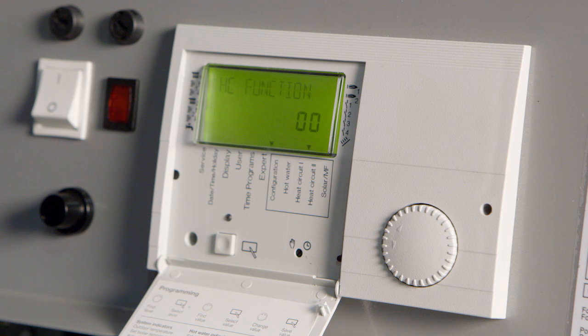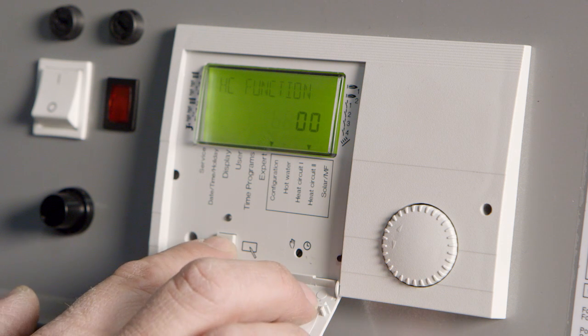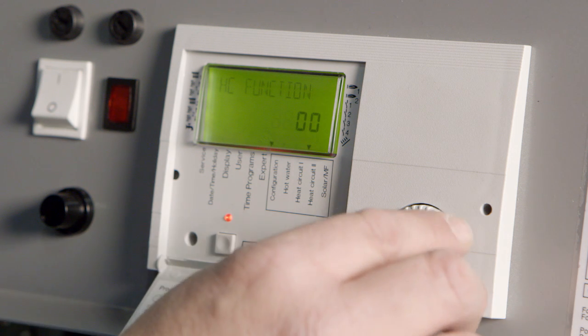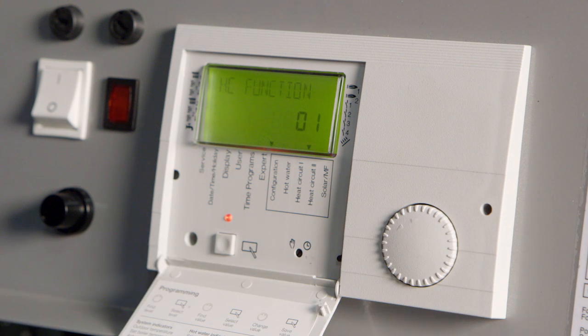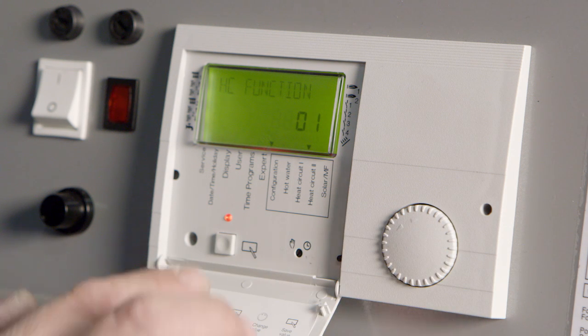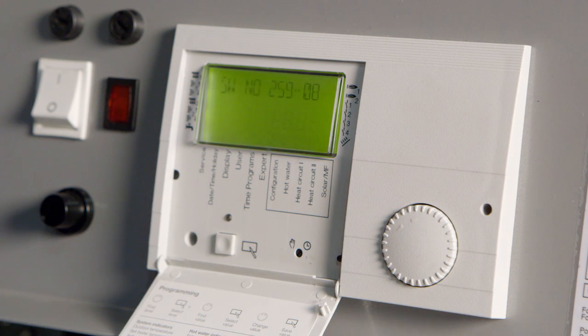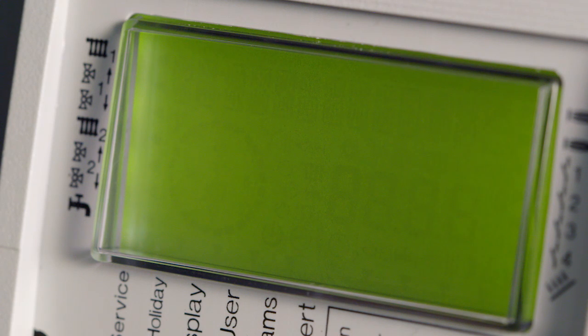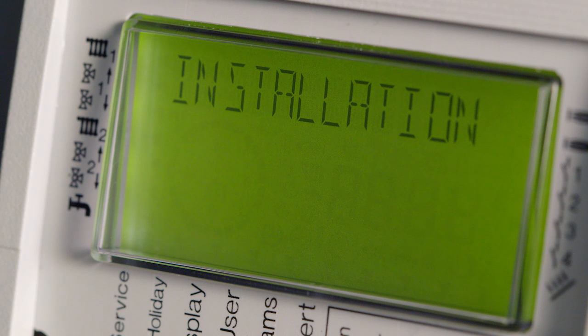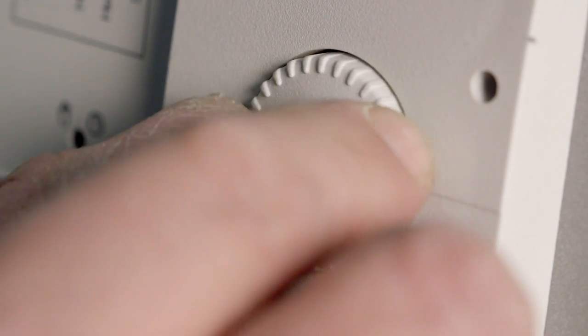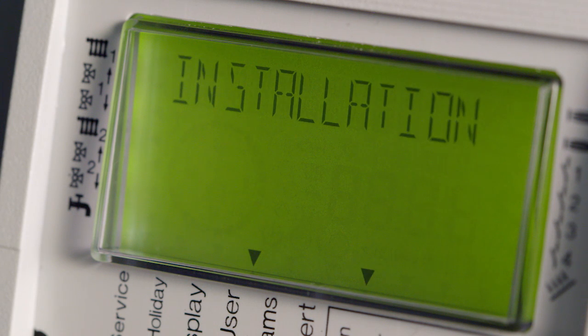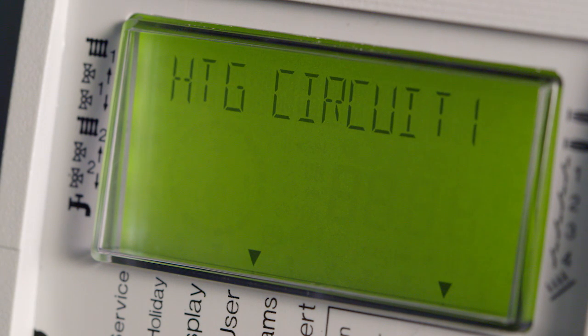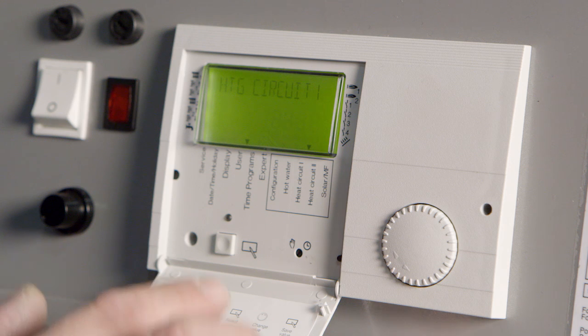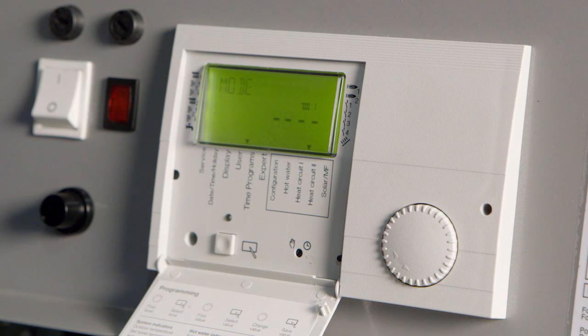With the heating circuit function up, press the program key. Turn the knob to change the heating circuit function to 01. Press the program key again to store this setting. The controller will reset. This is normal. After reset, the display will switch back to installation as shown here. Use the rotary knob to scroll to User and access Heating Circuit 1 as the submenu. Press the program key to enter this submenu.